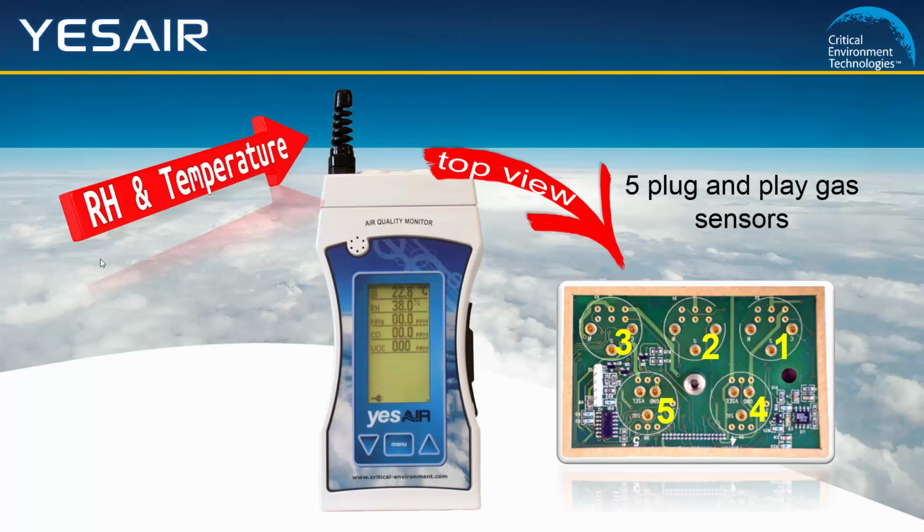Calibration should always be performed by a trained and experienced technician. Temperature and RH sensors must be calibrated using a special chamber and cannot be calibrated in the field. Only gas sensors can be field calibrated.